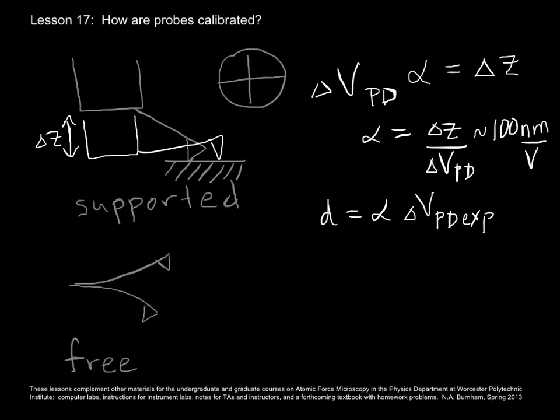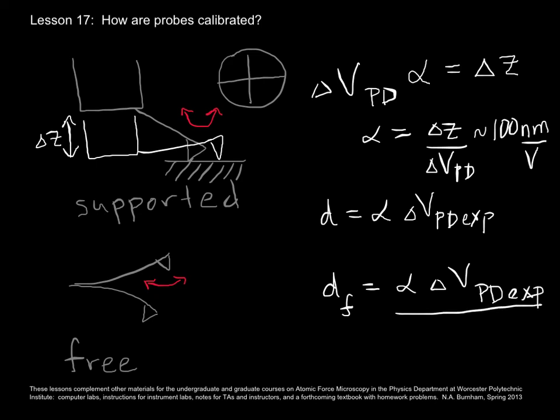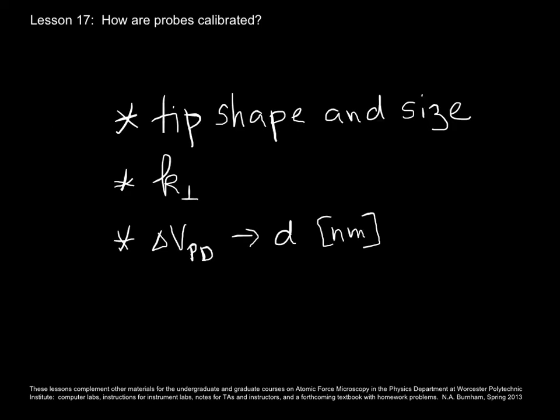If you're interested in the deflection of your cantilever when it's free or mostly free, that is slightly different from the situation that we just did, the supported situation, when the cantilever tip is in firm contact with the sample. In the free case, the angle at the end of the cantilever does not change quite so much as in the supported case. So now, for your deflection, what you do is you take the equation we just got and divide it by 1.09. 9% difference there.